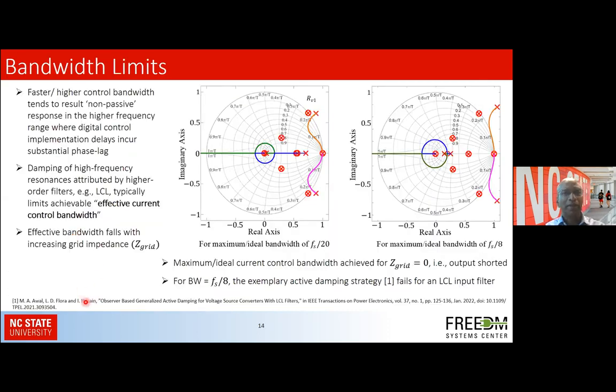So where does the bandwidth limit for the current controller come from? We worked on a research paper on observer-based active damping, which we actually use in most of our controllers for our inverters that are grid connected. Here, through an example, we show that for this particular hardware topology, if we have a bandwidth of fs over 20, the poles quickly enter the unit circle from when the active damping gain is 0, which means it would be stable.